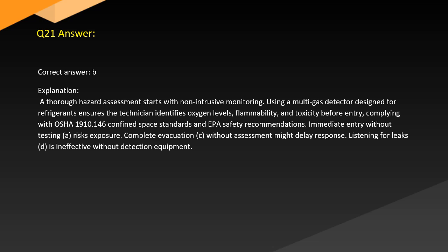Answer. Correct answer: B. Explanation. A thorough hazard assessment starts with non-intrusive monitoring. Using a multi-gas detector designed for refrigerants ensures the technician identifies oxygen levels, flammability, and toxicity before entry, complying with OSHA 1910.146 confined space standards and EPA safety recommendations. Immediate entry without testing, A, risks exposure. Complete evacuation, C, without assessment might delay response. Listening for leaks, D, is ineffective without detection equipment.